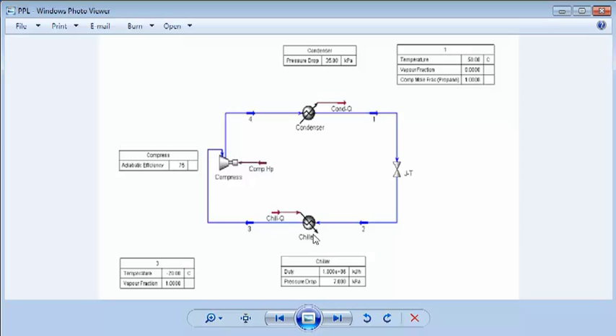Stream 2 enters the chiller and is further cooled. Our aim here actually is to meet up with the given dew point specification at point 3. The chiller cools the gas, bringing it to dew point specification at point 3. At this point, it does not need to do much work again as the JT valve has helped in reducing the temperature of the gas. Hence, we can save energy that would have been used to power a much bigger chiller that would have been needed to get the job done.